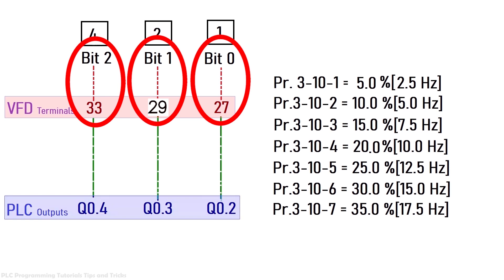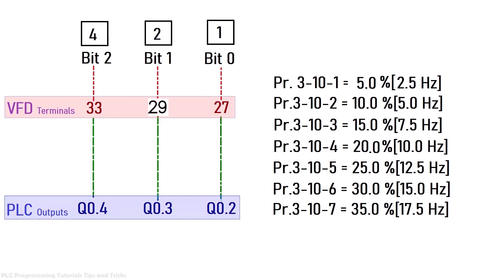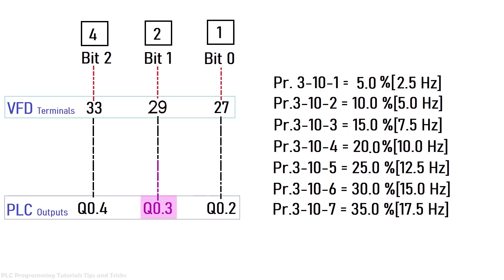As discussed, these three inputs of the VFD — 27, 29, and 33 — are the bits of a 3-bit binary number. Terminal 27 is bit 0 with value 1, terminal 29 is bit 1 with value 2, and terminal 33 is bit 2 with value 4. If we turn on only Q0.2 it activates bit 0 (value 1), loading preset frequency reference 1 — 2.5 Hz — and the motor will run at 2.5 Hz. If we turn on Q0.3 it activates bit 1 (value 2), loading preset reference 2 — 5.0 Hz.